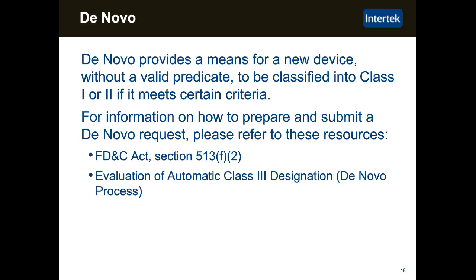However, the manufacturer can petition the FDA with evidence of low risk and high benefit. If the FDA agrees, the device is then classified into a lower class, and the fee for the petition is really not significant or doesn't exist at all, but you will have to pay the fee for the 510K. But it's certainly worth the effort because there's a significant difference between the fees for a 510K and the fee for a PMA, as well as the regulatory requirements are significantly greater for the PMA. So if you have a device and you're unable to identify a predicate that's substantially equivalent, we recommend that you take advantage of the law as it's read in Section 513F2 and undertake a de novo classification.